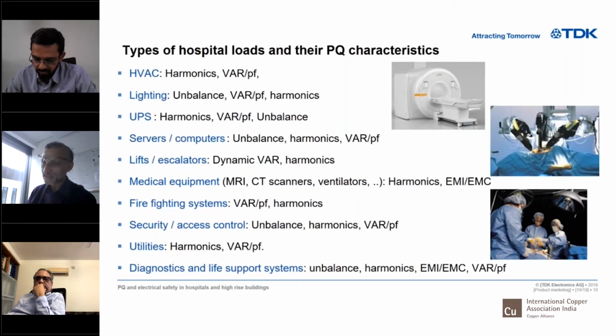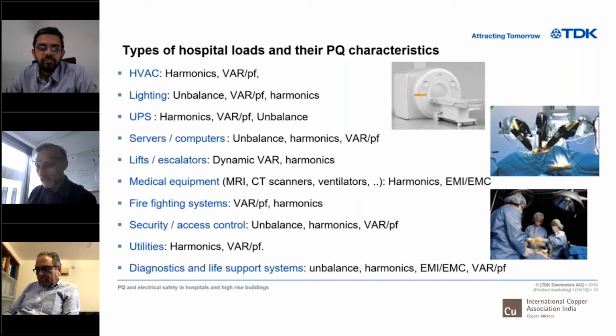Firefighting systems, access control, security control, utilities like water pumps, motors, etc. And most important is the diagnostics and life support system. And all of them are again single phase. They create unbalance. They have switched mode power supplies, and they are very susceptible to EMI, EMC, and most of them have a very low power factor. These are the typical loads you have in a hospital.